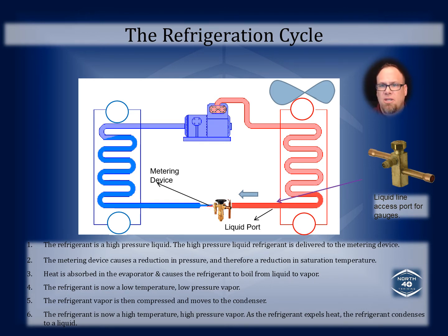And then in addition to that, it also assures that by the time the refrigerant gets to the compressor, it is in a vapor form. We don't want liquid going to the compressor because liquid doesn't compress well. If you don't believe me, we all know, and maybe we are those people that turn the refrigerant tank upside down and charge in liquid form with no throttling valve on there.